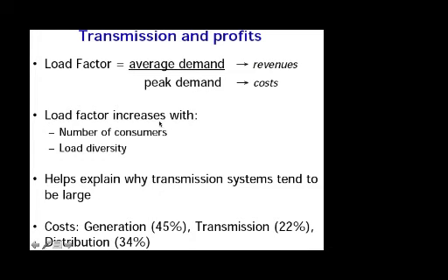The load factor increases with the size, the number of consumers, and the diversity. Because imagine that, even for my small electrical needs, I need 2,000 watts at one point, for instance, when I run my microwave oven. So that would mean I need to have 2,000 watts of capacity if it were just for me, even though I use on average 100 watts. However, if we load in 35 million people, it's very unlikely that all these different people are going to start their microwave ovens at the same time. That will increase your load factor.